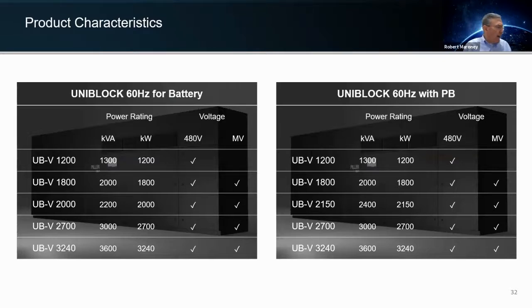So let's start looking at product characteristics. When we talk about the sizes that the UPS comes in, they go from 675 kilowatts all the way up to 3,240 kilowatts, single module systems, okay? So you can do them in low voltage, 480 volt or 600 volt, and you do them in medium voltage. In medium voltage, you can do any voltage that you want to do.